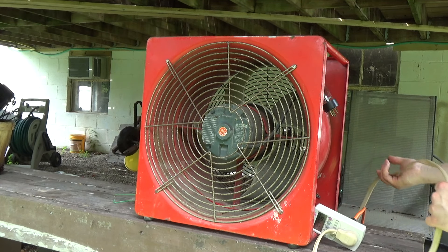I can't even stand in front of it — pulling the volts down pretty good. Only 114 volts at the outlet now. Amps are 6.08, 500 watts, power factor 0.72. It's running a little bit over spec, especially considering the voltage is low.